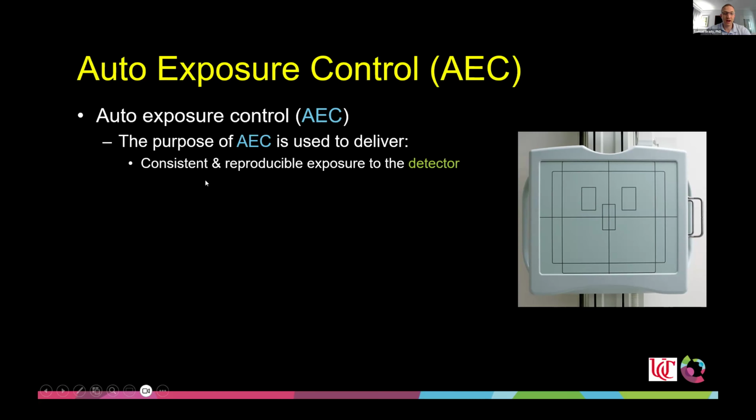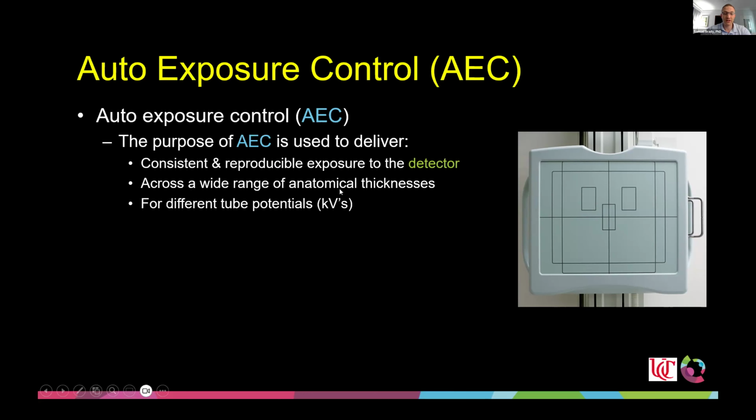And this ensures that we are consistent and we have reproducible exposure to the detector, no matter the size or thickness of the patient, no matter the kV that we select, low or high, and no matter the skill level of the operator. And using AEC is a great way to try to keep consistent image quality across your entire patient population.